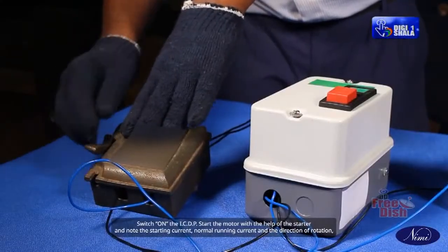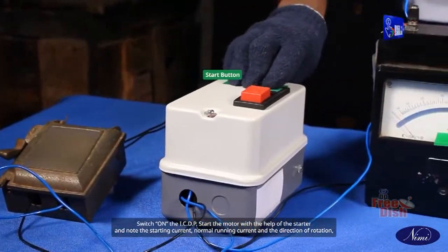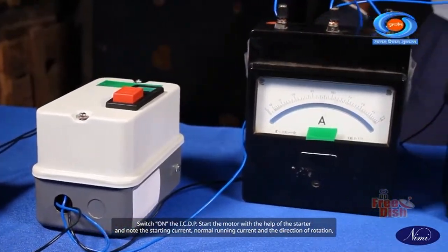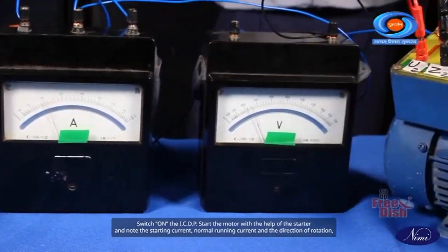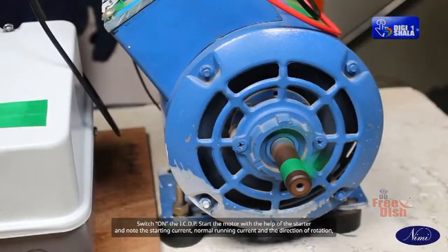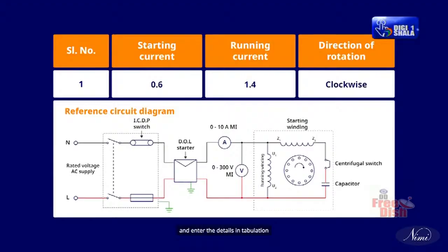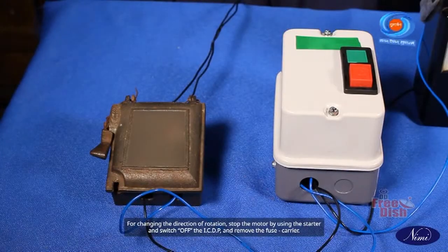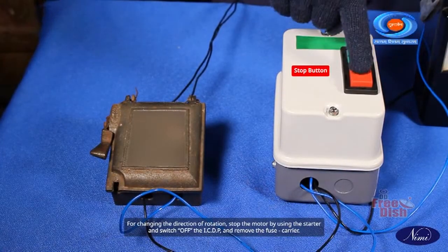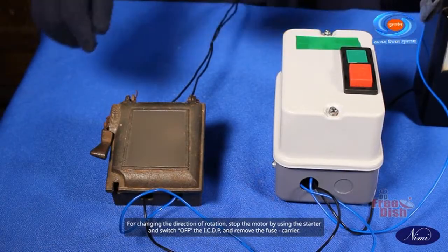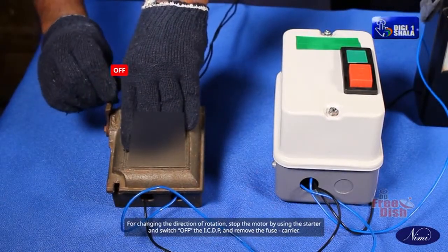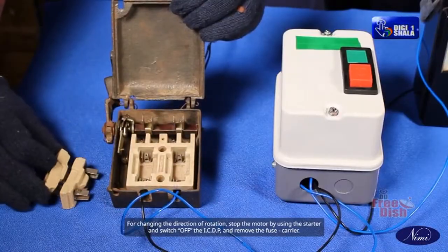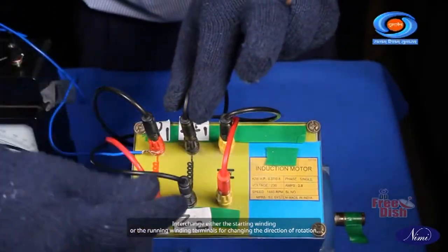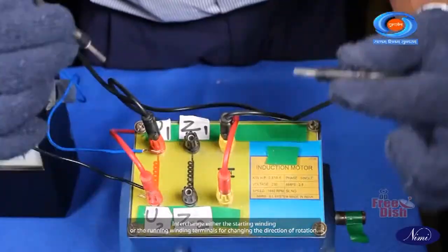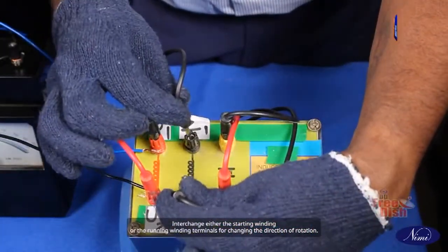Switch on the ICDP, start the motor with the help of the starter and note the starting current, normal running current and the direction of rotation, and enter the details in tabulation. For changing the direction of rotation, stop the motor by using the starter, switch off the ICDP and remove the fuse carrier. Interchange either the starting winding or the running winding terminals for changing the direction of rotation.